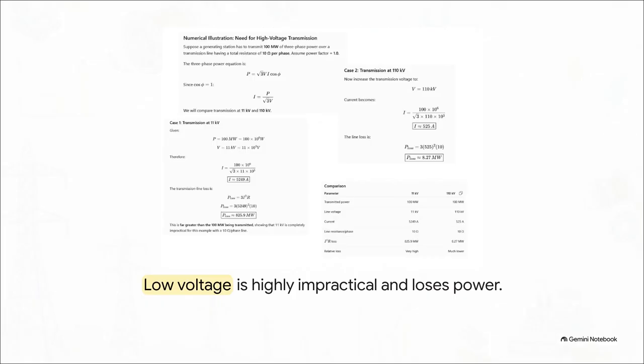When you run the numbers, the culprit becomes clear. To deliver 100 megawatts at a relatively low 11 kilovolts, the current has to skyrocket to over 5,000 amps. Since power loss through wire resistance relies heavily on the current flowing through it, we end up with that massive 825.9 megawatt loss. This proves that low-voltage transmission for long distances isn't just a little inefficient—it's literally impossible. It fails spectacularly.